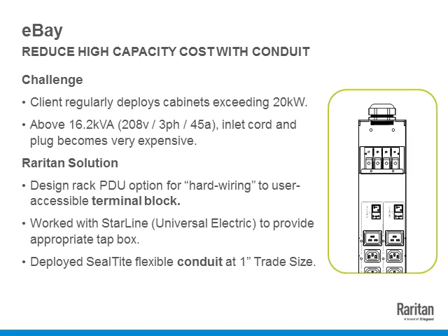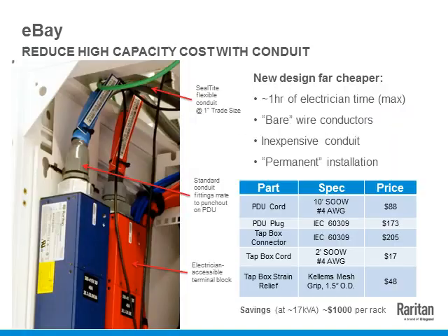And then finally, we used conduits. What a creative idea in a data center. Conduits to terminate power whips into the power strips instead of using the standard power cords. Let's look at the details behind it, and this will be very interesting in terms of what the savings were.